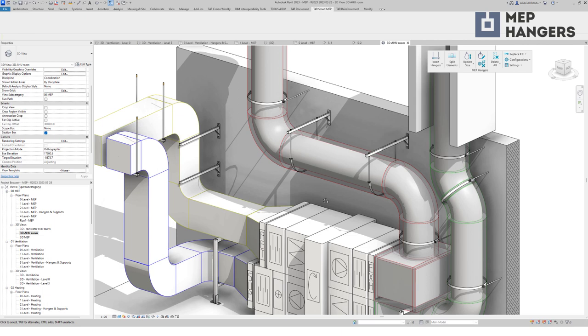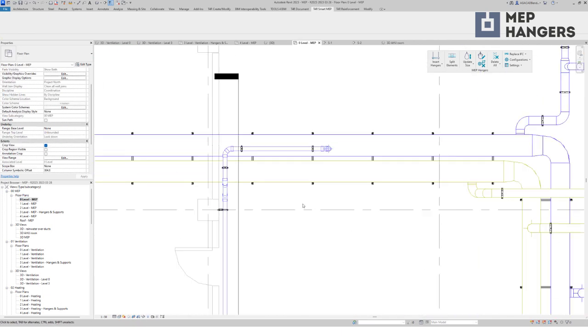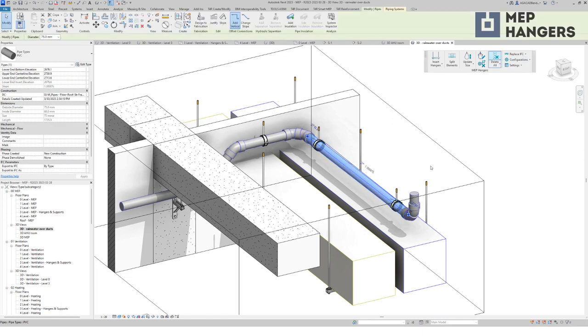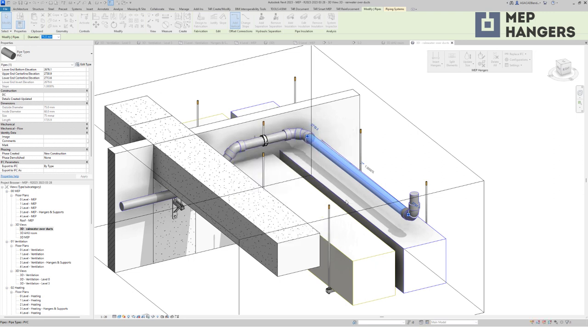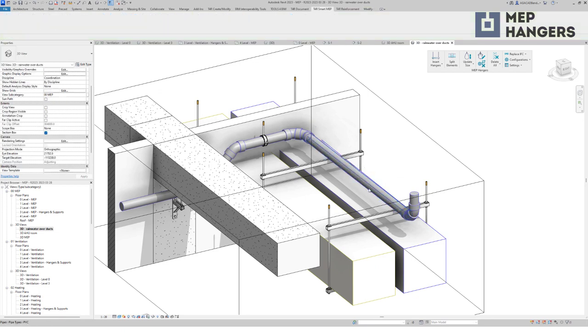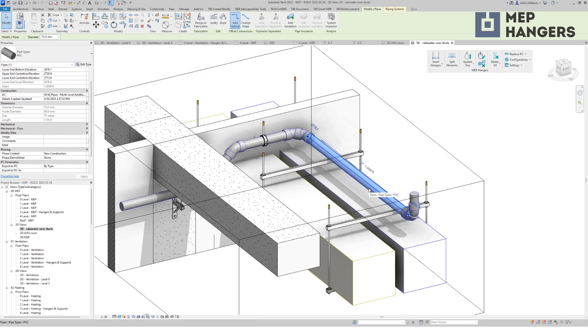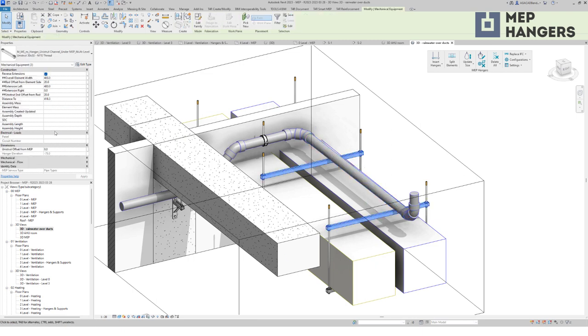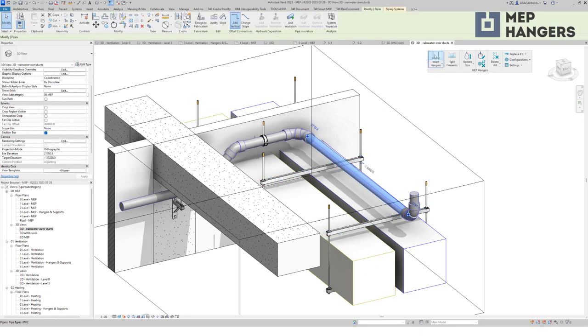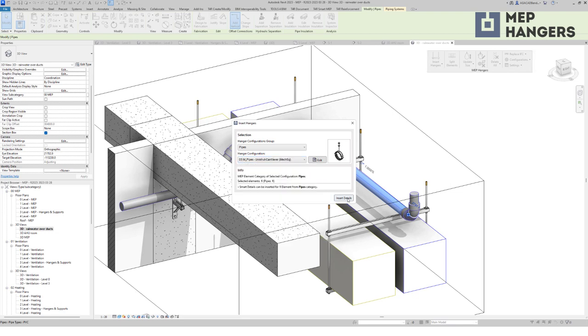Now let's go back to the rainwater system. The pipe goes over the ducts that are supported. I have a 3D view of this section. I will delete hangers from this pipe, and then run a configuration which will place Unistrut channels to the existing Unistrut frame. I can make this a more rigid support as well — I will select the Unistrut channels and offset them down by 50mm. Then I can run a configuration to find these Unistruts.